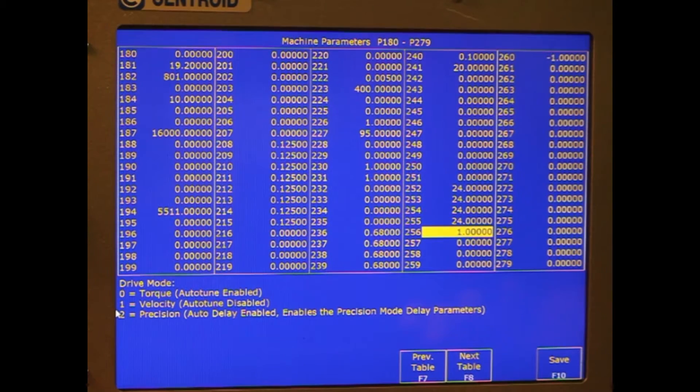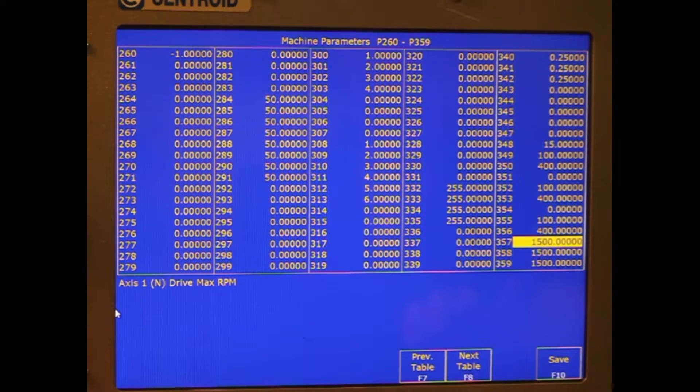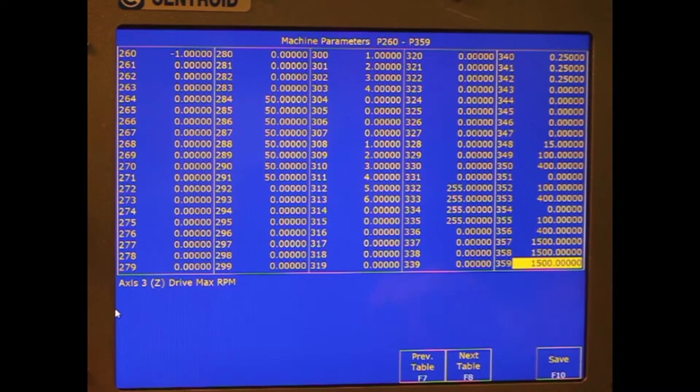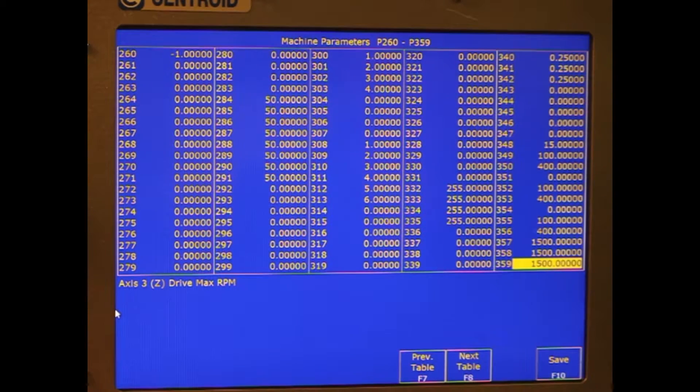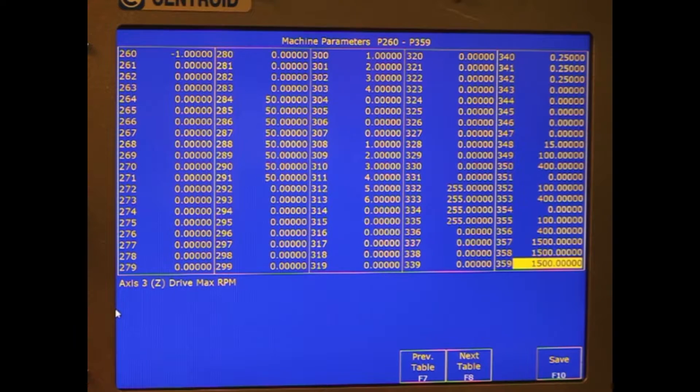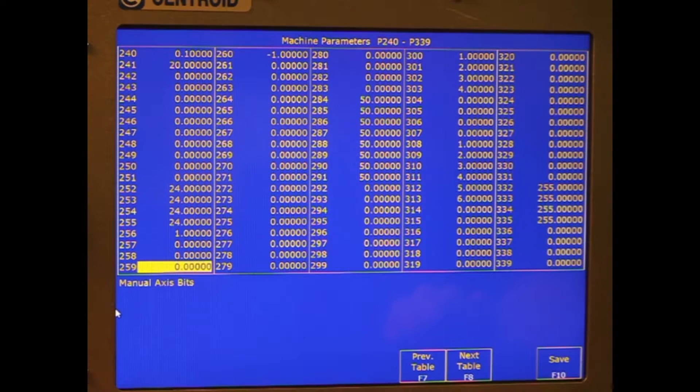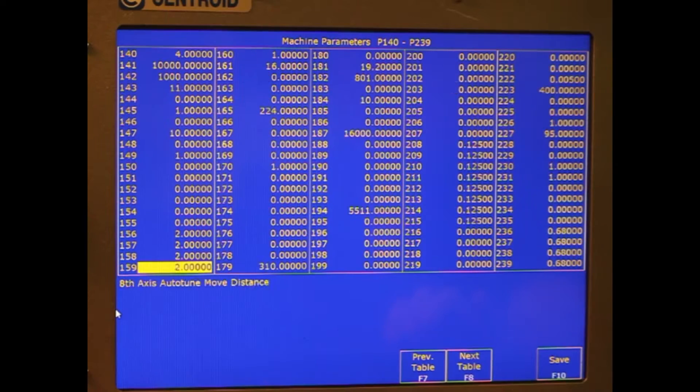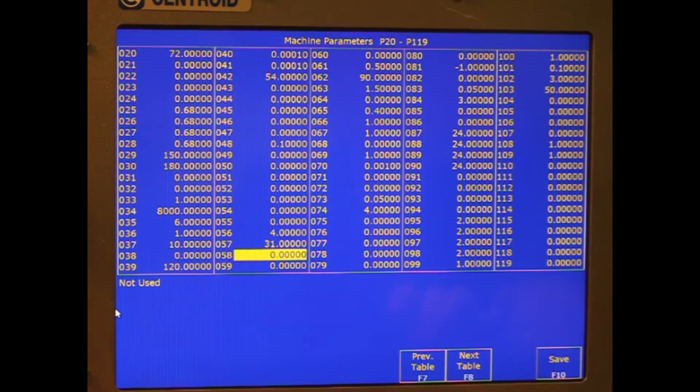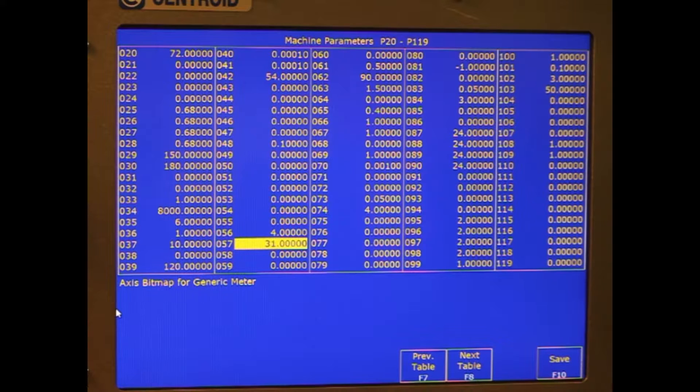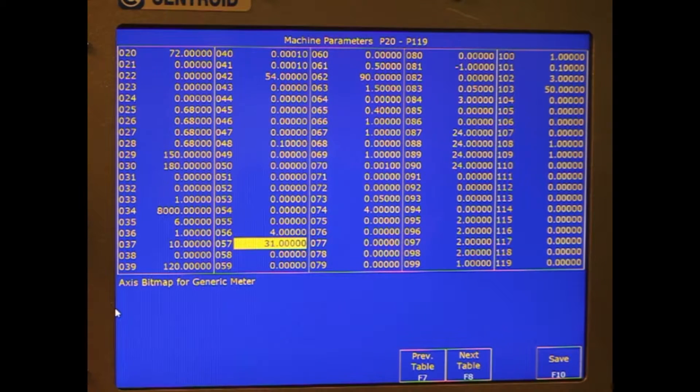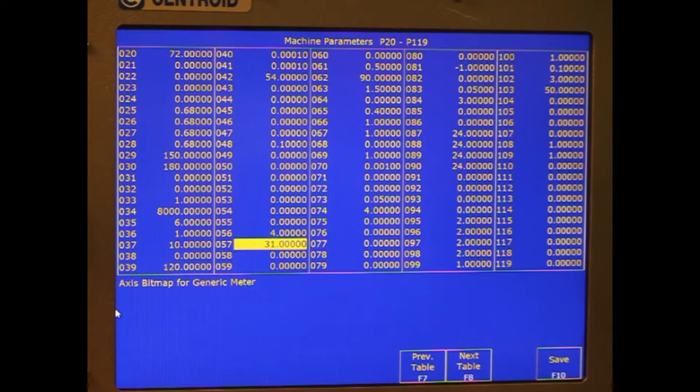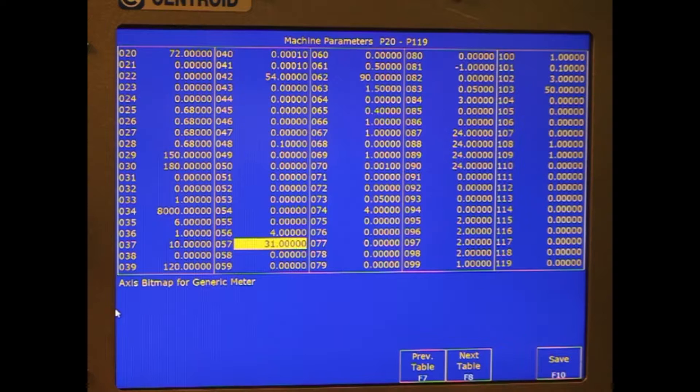Then we need to go to parameters 357 through 359, which are the max RPMs of the drive. On this setup it's 1500 RPM. Then we need to go to parameter 57, which is set up for load meters if the machine is going to use those from the servo drives, which this one is. If we set that to 31, that is set up for all the first five axes all being used for the analog input from the drive.